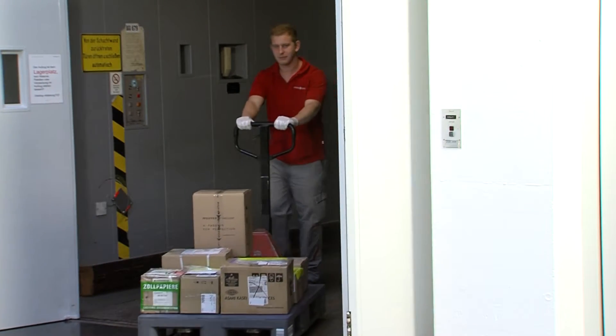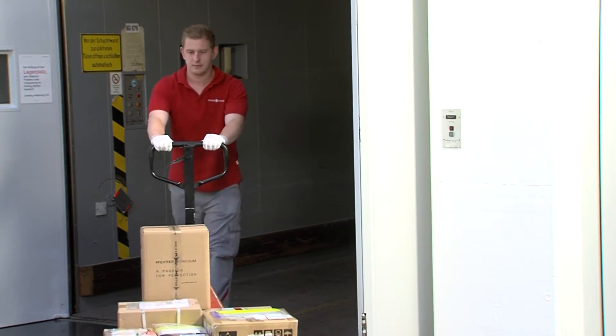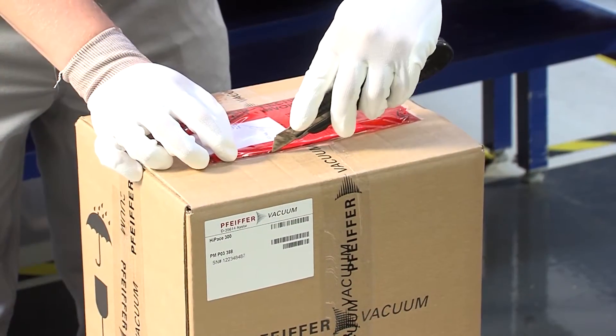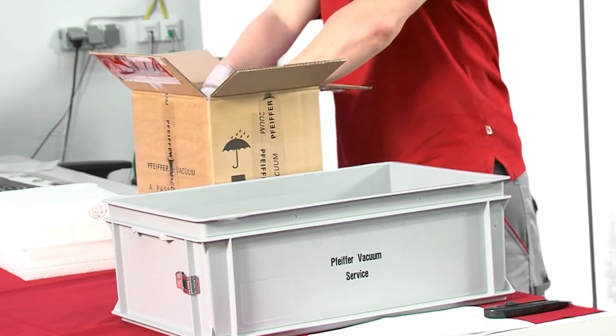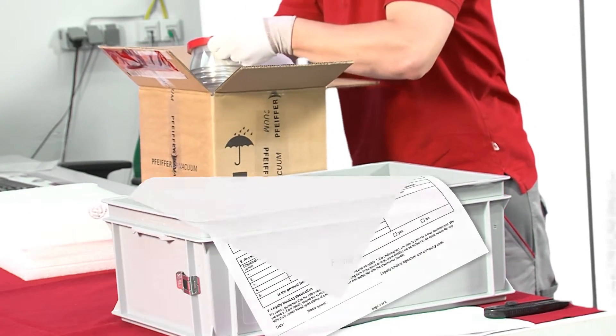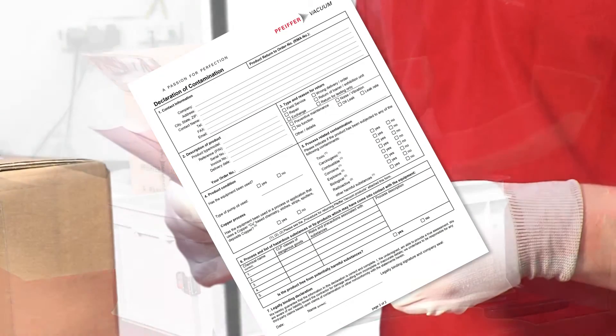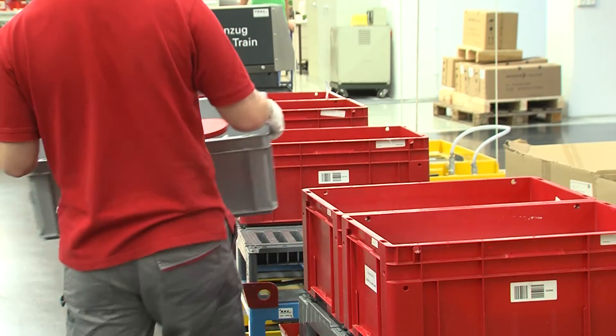If a pump is not working properly, as in the case of this HiPace 300 Turbo Pump, the main priority is to keep downtime at a minimum. When the pump arrives at our service center, it is registered and inspected. The declaration of contamination must be provided by the customer prior to any repair work to ensure the technician's safety.